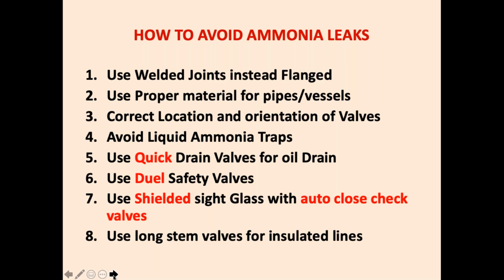I did a lot of projects in Porbandar and these areas, and you will be surprised that people there were using GI pipes for ammonia plants. So I said, what is this? Why are you using GI pipe? He said, GI pipes are thicker than the steel pipes, so we use it. But they don't realize that it is not at all suitable. All that galvanizing will go into the compressor because it is galvanized on both sides, and this pipe is not at all suitable.